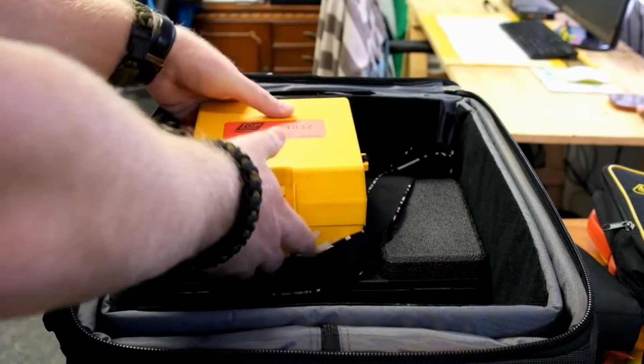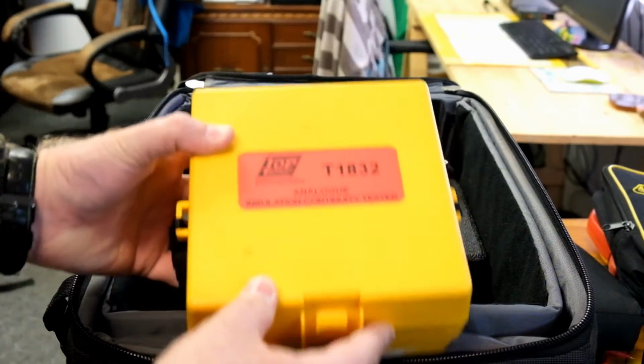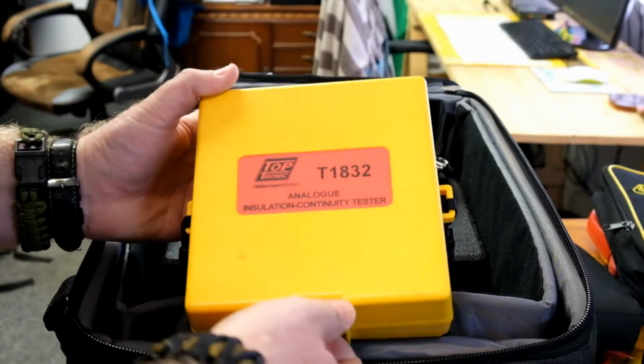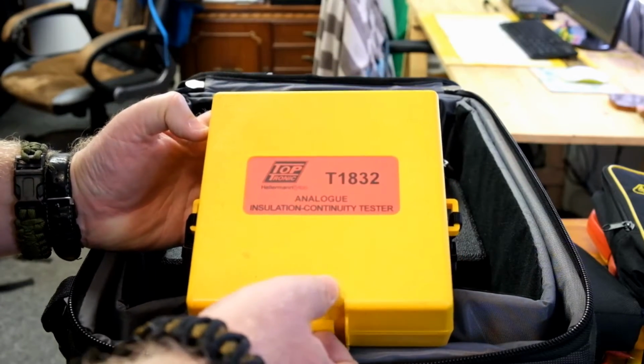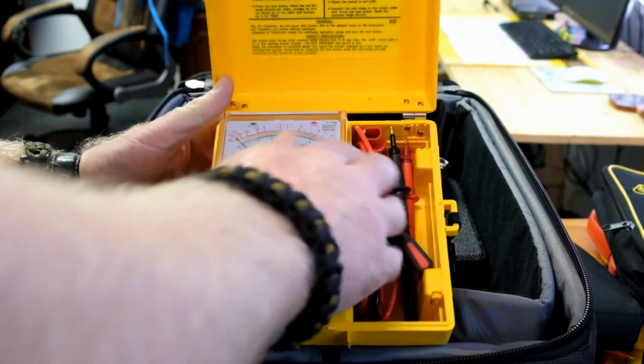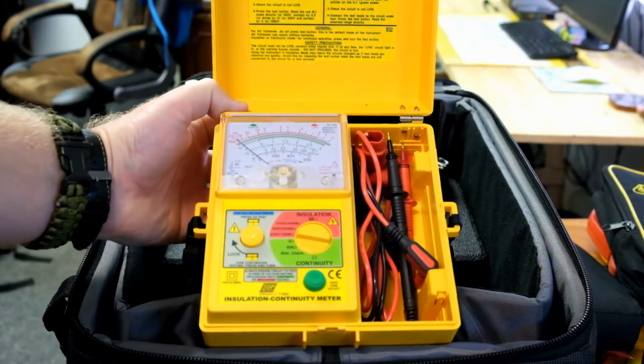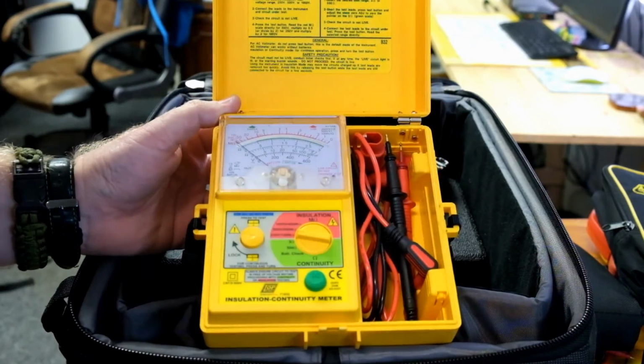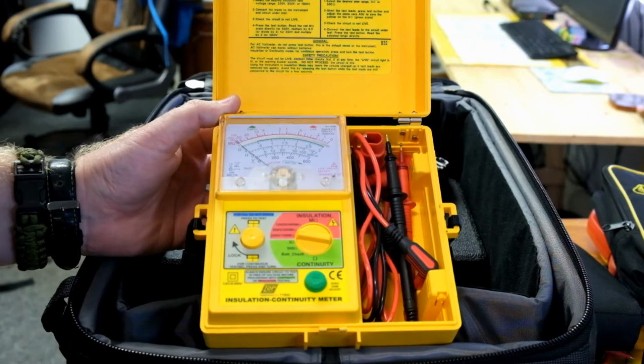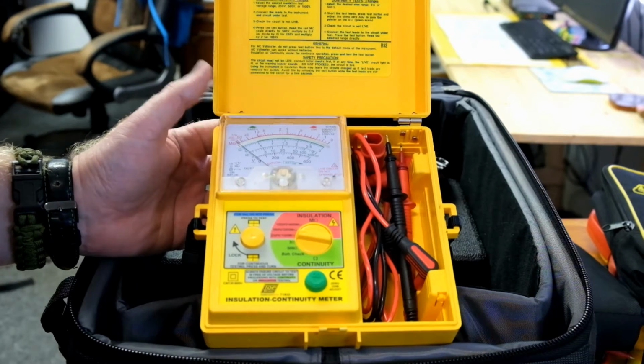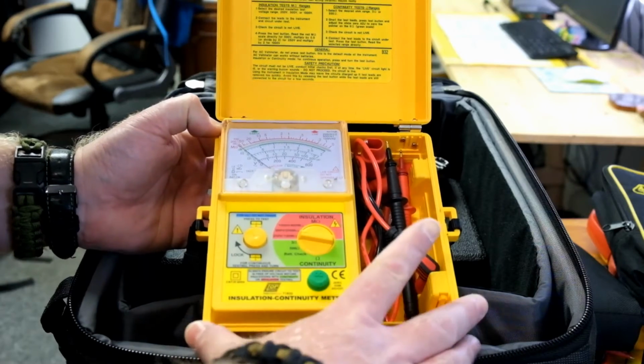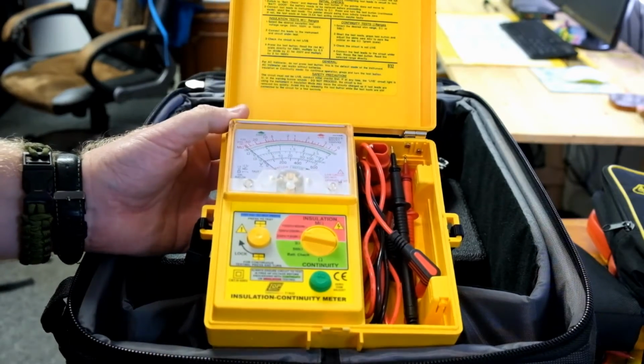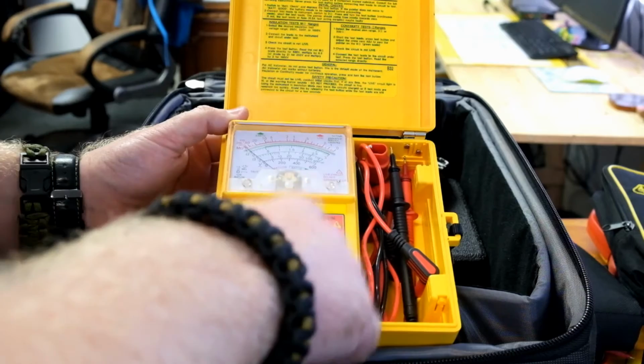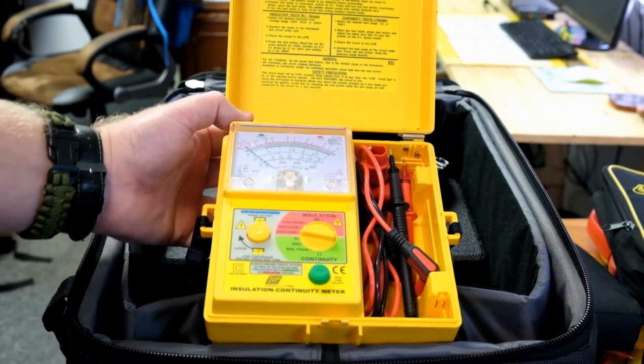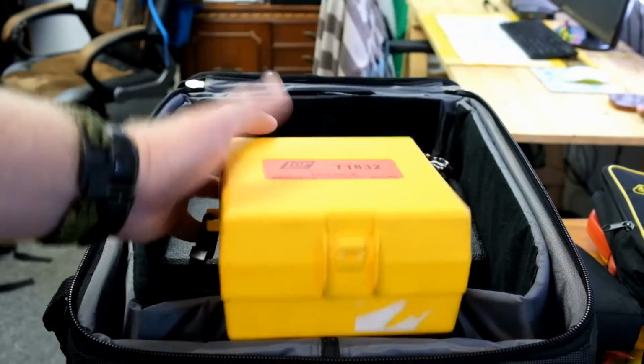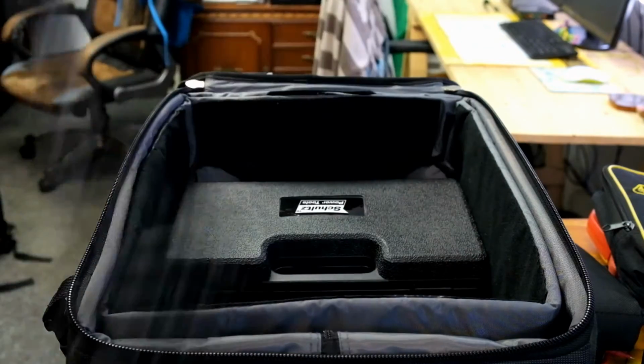Then we have the analog one—why analog, you may ask? Just because I can. This is the Toptronic T1832 insulation continuity tester, used for testing insulation resistance. It's also a really good voltmeter for carrying around and checking AC mains and similar issues, but it's mostly used for 250, 500, and 1000 volt insulation resistance tests, just to check there are no issues with the installations.